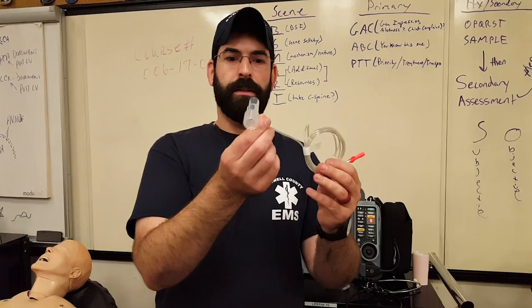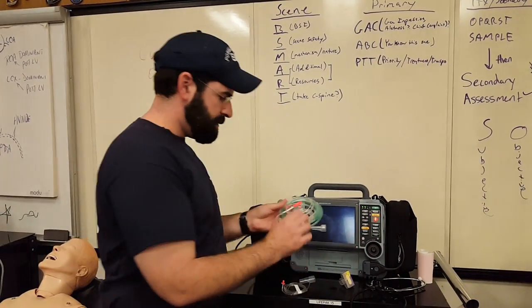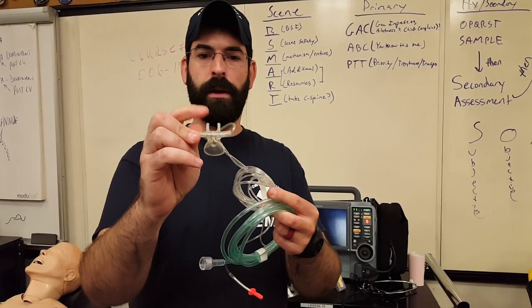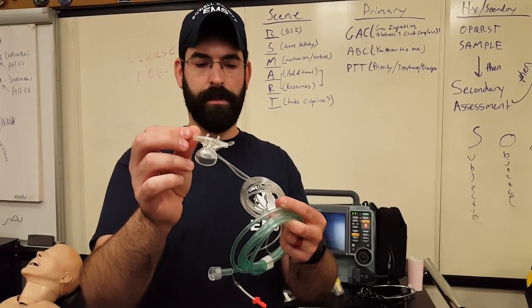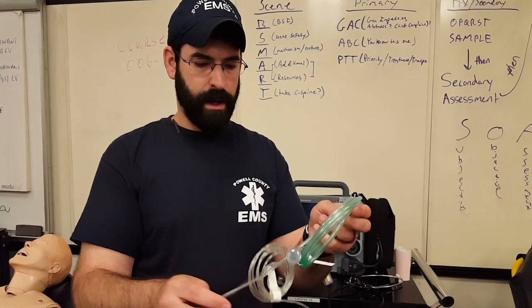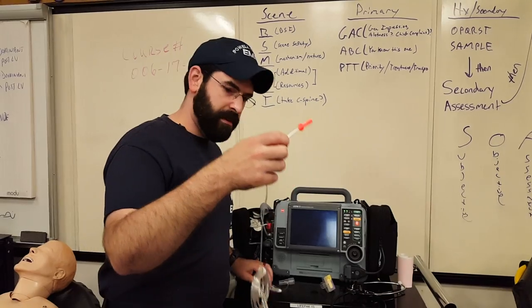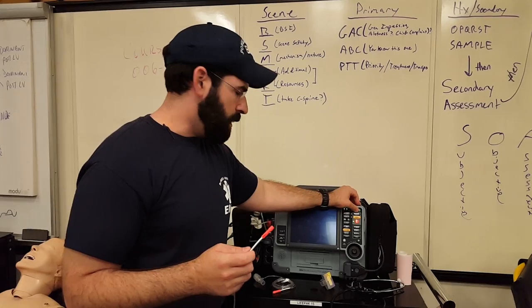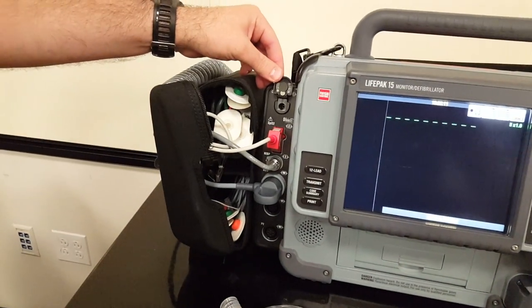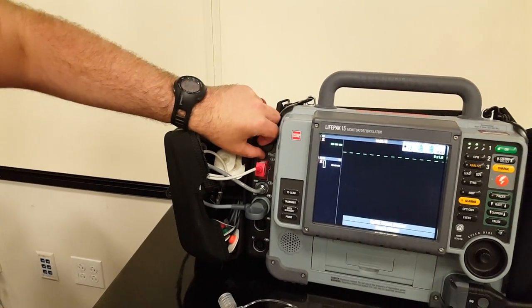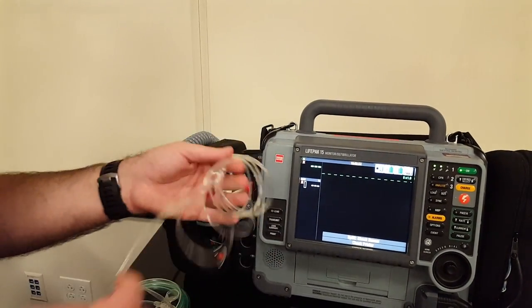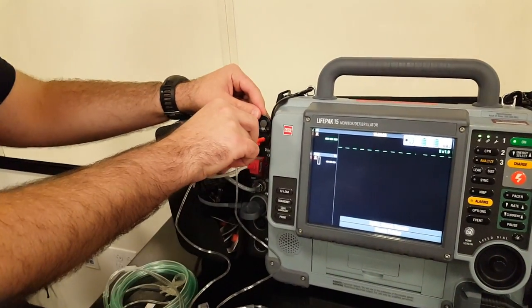The other kinds of monitoring devices we have are an inline CO2 device and a sidestream end tidal CO2 device — the so-called combination nasal cannula and end tidal device, with traditional nasal cannula prongs and a little sensor to pick up the end tidal CO2. Whether you're doing sidestream or inline monitoring, these things get hooked up the same way. Find the little orange tip — both the sidestream and the inline have the same orange tip — and plug it into the little port right above the SPO2 connection. It has a little magnetic cover to keep it safe.